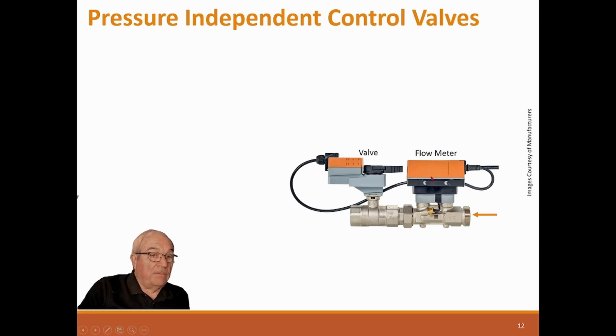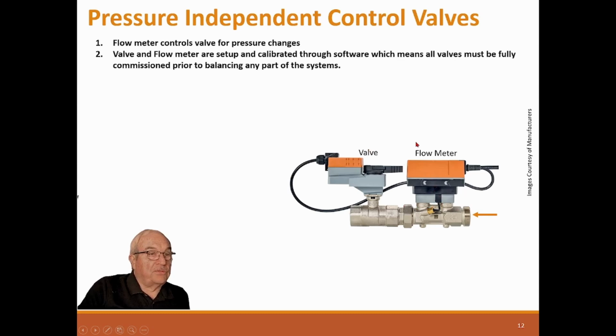I have had problems with them, so we'll talk a bit about that. The flow meter controls a valve for pressure changes. So if the water pressure changes, say some other valve's closing off, then it will close this valve down to maintain its flow as constant. Valve and flow meter are set and calibrated through software, which means all valves must be fully commissioned prior to balancing any part of the system.